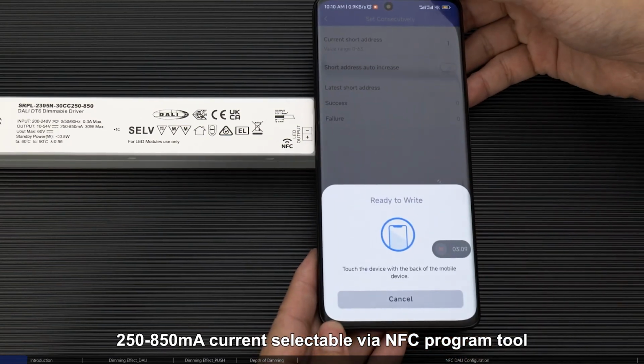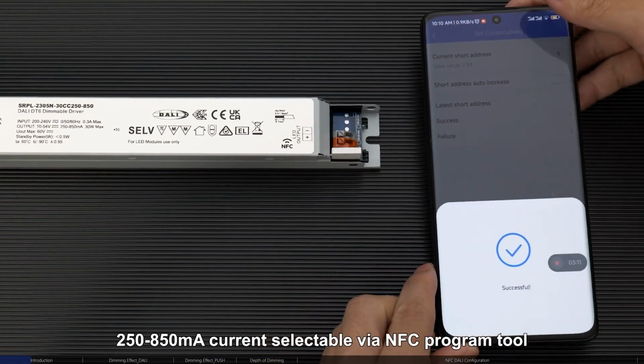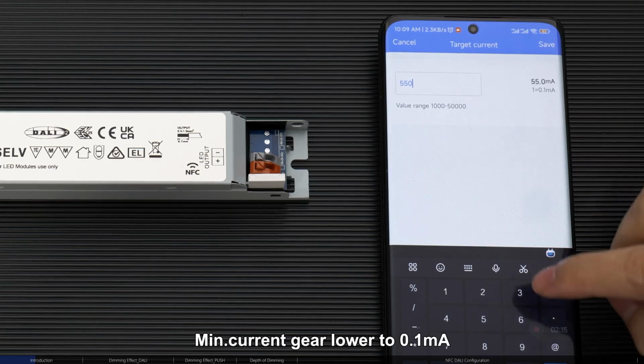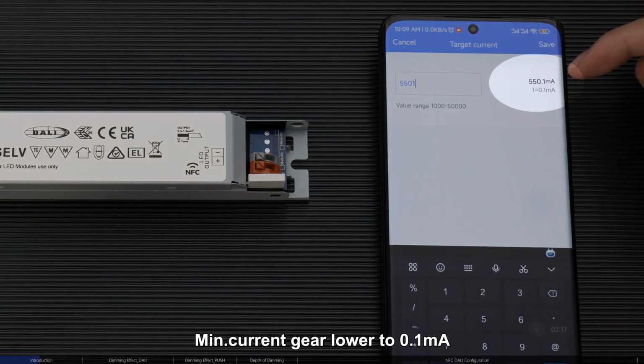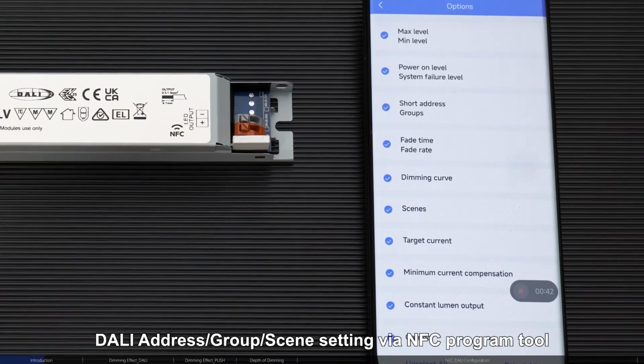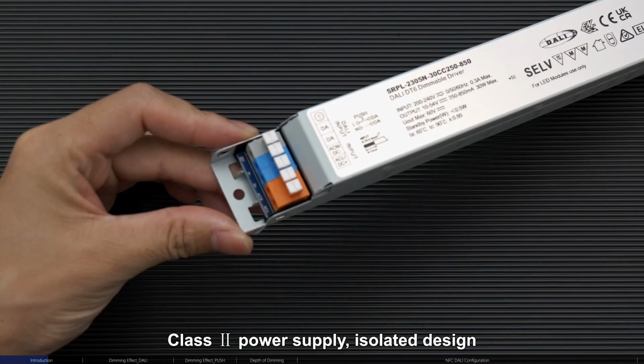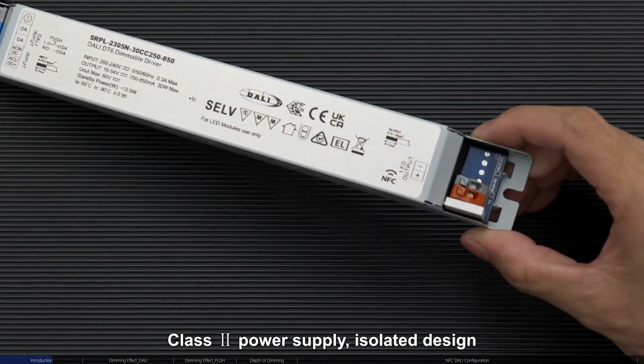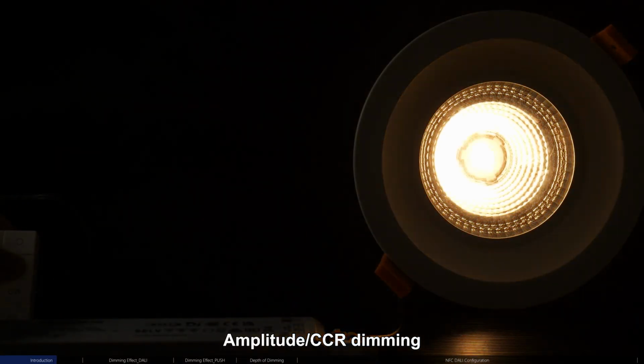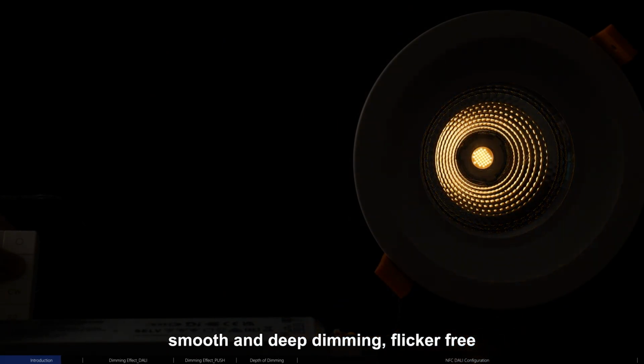250 to 850 milliamperes current selectable via NFC program tool. Min. current gear lower to 0.1 milliamperes. DALI address, group, and scene setting via NFC program tool. Class 2 power supply, isolated design. Amplitude CCR dimming, smooth and deep dimming, flicker-free.